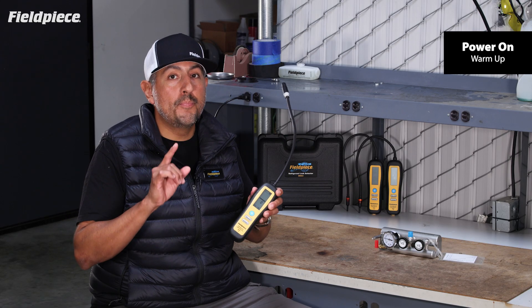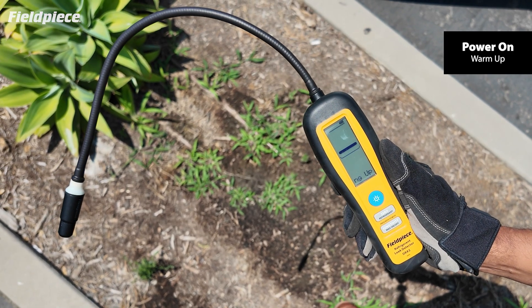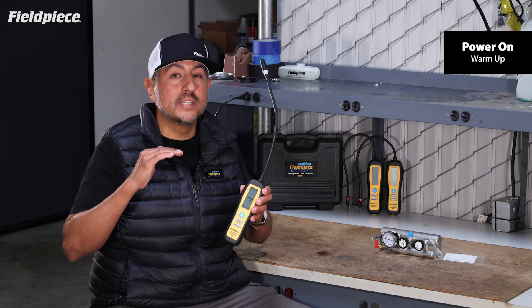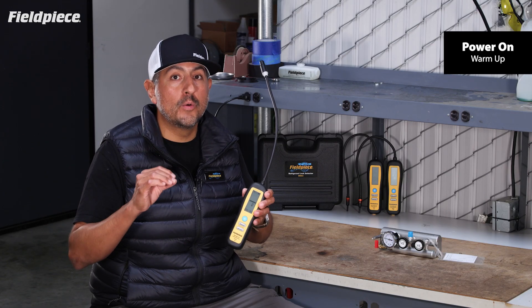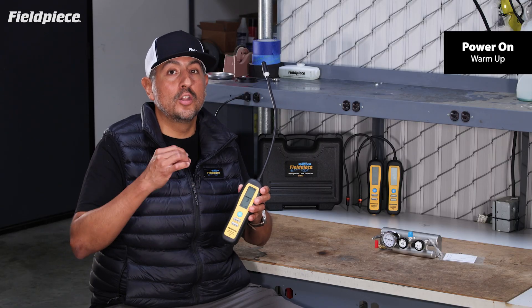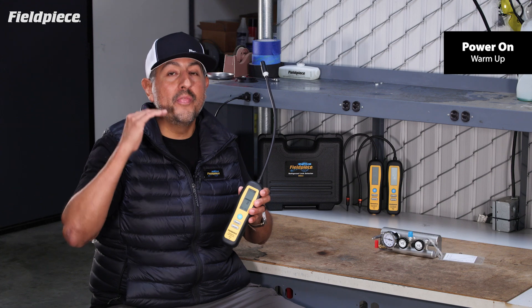First, ensure that you power on your Fieldpiece Refrigerant Leak Detector in fresh air to ensure that when the warm-up period is complete, it has set its initial sensitivity baseline to zero refrigerant in the air. That's key because the leak detector alerts when it senses higher levels of concentration than that initial baseline.